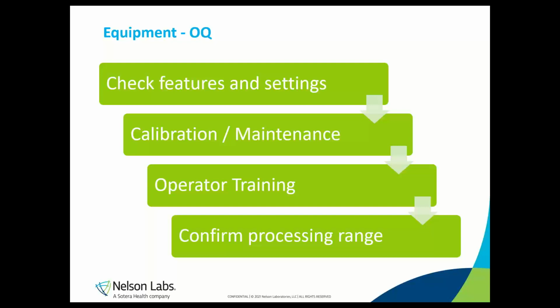We've been asked if you need product in the packaging or if you can use empty packages for the sealer qualification. Well, the answer is you can use empty packages, since the purpose of the sealer qualification is to show your sealer can make good seals, and that's really independent of the product. However, you must include the product in the packaging validation, as we discussed in the Part 1 webinar, and that will show that your packaging can be sealed properly with the product inside.